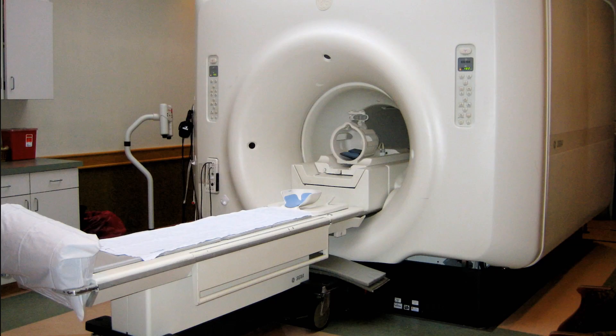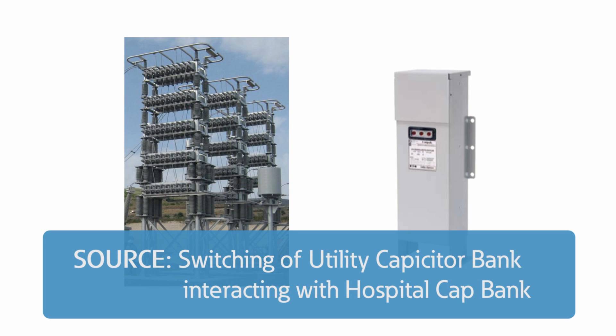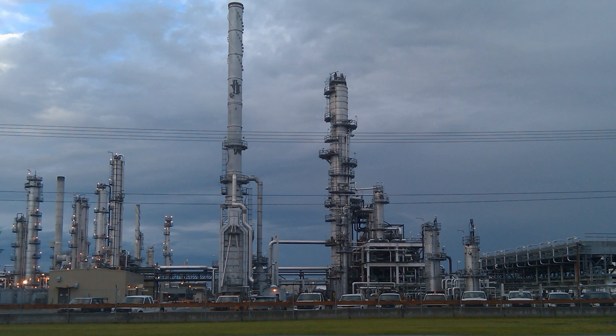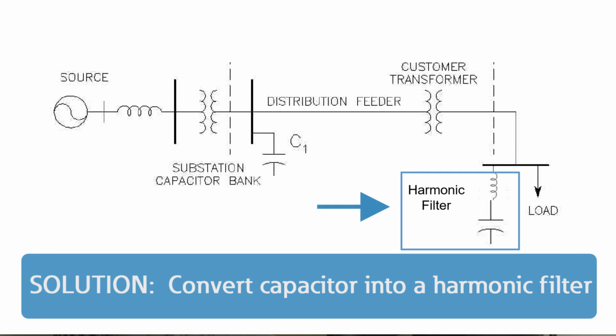Did you just apply a surge protector? No — in this case it required some detailed analysis. The symptom was the misoperation of MRI and CT scanners when the switching occurred, causing disruption and sometimes physical damage. The source was the utility cap switching, but it was related to the low-voltage cap in the hospital. We've seen this in other facilities like refineries and industrial plants using power factor correction caps. The solution was either to remove the low-voltage cap or make it into a detuned filter to move its resonant point so it wouldn't amplify the transient.